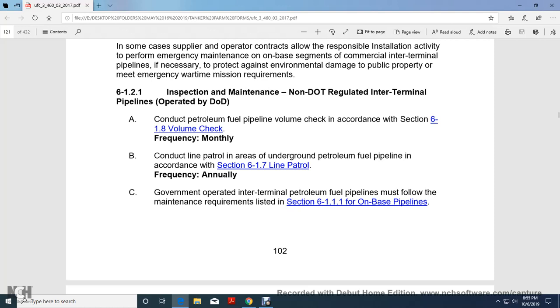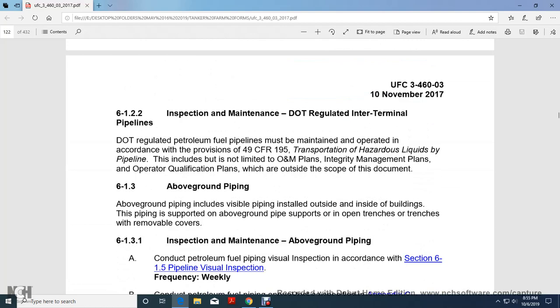Conduct the petroleum fuel pipeline volume check in accordance with 6.18, volume check frequency monthly. Conduct a line patrol of the area of the underground petroleum fuel pipeline in accordance with 6.17 line patrol, frequency annually. Government operated inter-terminal petroleum fuel pipelines must follow the maintenance requirements of 6.11.1 on base. All right, 6.12.2 inspection and maintenance of DOT regulated inter-terminal pipelines.